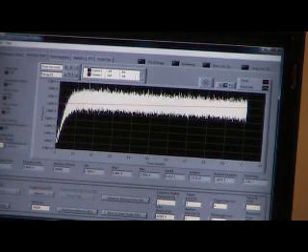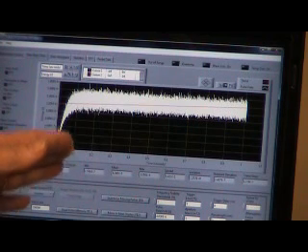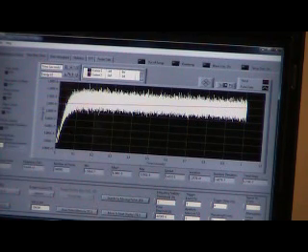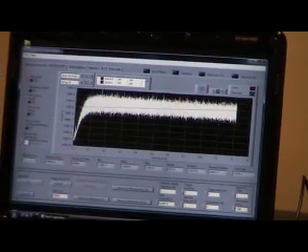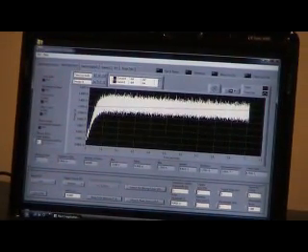I want to emphasize again, any joule meter you go out on the market to purchase right now, and you want to catch every single pulse, you're talking about thousands of pulses per second, not hundreds of thousands of pulses per second. If you look at the time scale down here, this is a millisecond. All of this information is captured in less than the first 100 milliseconds. If you're using a power meter, you're never going to see this. If you're using the second fastest joule meter on the market, you might see a little bit of that. You'll never see this. This is the only instrument capable of showing you this type of information on your laser.